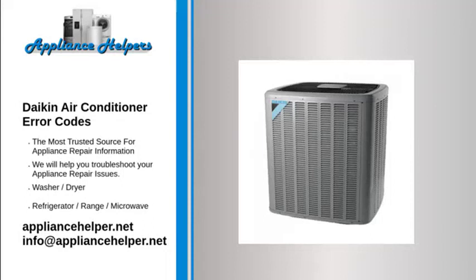Code AJ. Problem: malfunction of capacity setting. Indoor unit PCB: capacity setting adapter is not installed when replacing PCB. Defect of indoor unit PCB. Code C1. Problem: failure of transmission between indoor unit PCB and fan PCB. Defect of transmission of fan motor control driver.